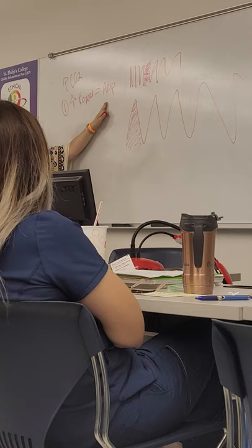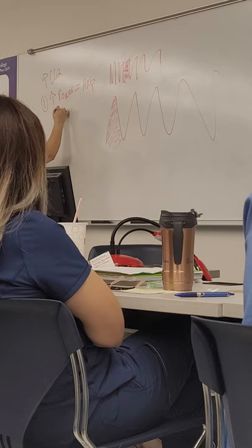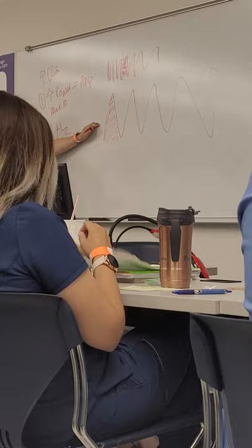But your power knob has a max of 10. And if you go up and up and up and up on your amp and you get to like what you think is max, then what's your second option? Your hertz. But what are you doing with your hertz? It increases your width. It looks like that. It increases your tidal volume when you go down on your hertz. And then it still doesn't work. You do it a couple of times and it still doesn't work. What are your other options?